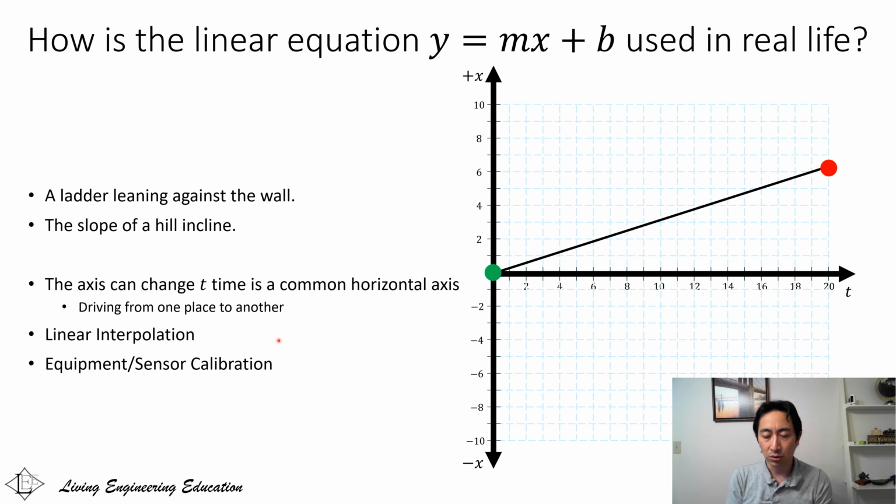The temperature measuring tool is often calibrated by measuring at boiling water and measuring in an ice bath. So you know 0 degrees and 100 degrees Celsius are 2 good reference points. And you take the raw data from the sensor and you use this simple equation y equals mx plus b to help calibrate. So at any other temperature, you would do a direct relationship with the calibration curve and find out what temperature the tool is actually measuring.